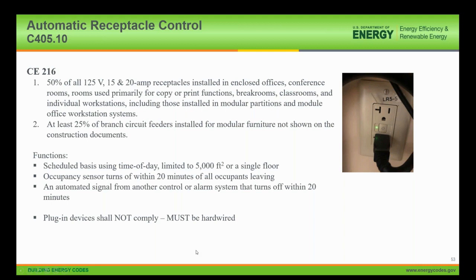The other change in the power and electrical section is the addition of automatic receptacle control. The image on the right is from a project I've worked on, just showing how it works. One of the outlets is in a 24/7 operation, meaning it's always getting constant power. The other one is switched off when the space is unoccupied. I recently completed a project where 55% of the energy was being used when the building was completely closed. So it definitely demonstrates there's good potential for savings there.